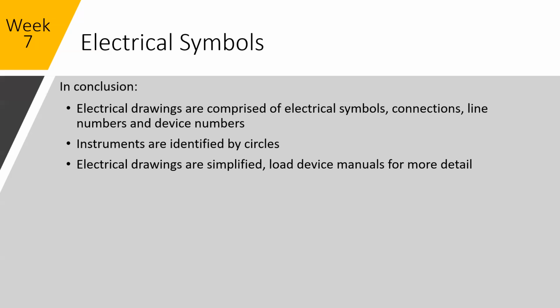Electrical drawings are simplified, conceptual drawings for wiring the facility, to know where the different power is, 600 volt, 120 volt, and control circuits. But when you get down to more detailed wiring, you need to look at more detailed loop drawings or the manuals for those particular devices. Any questions?